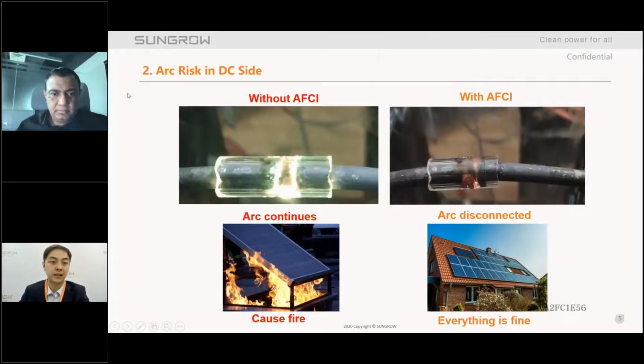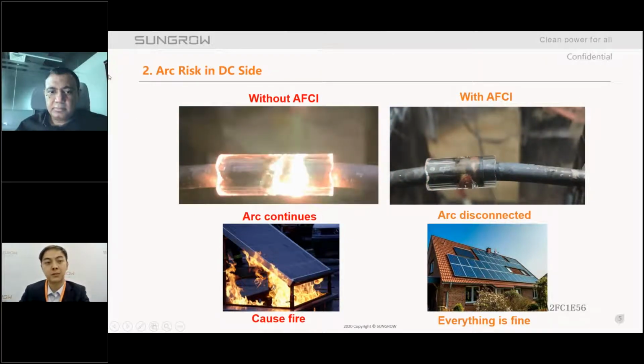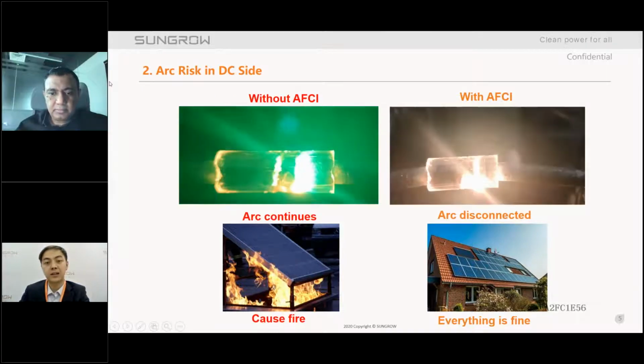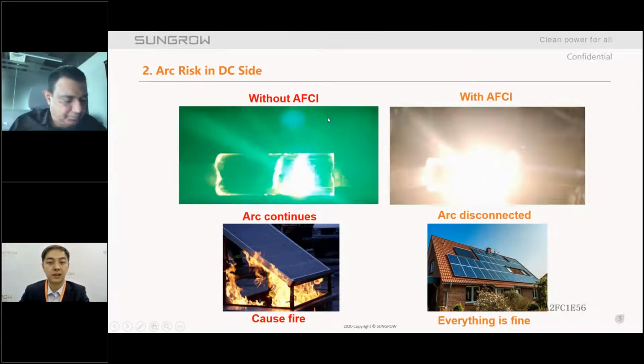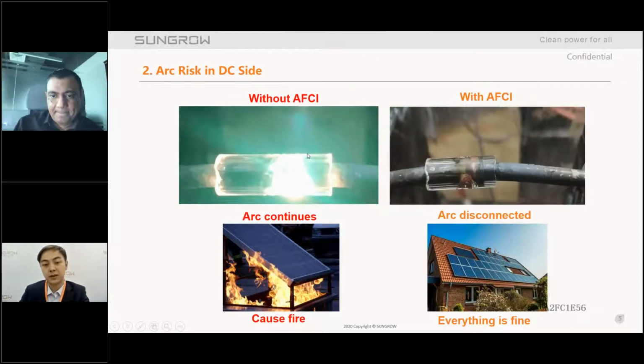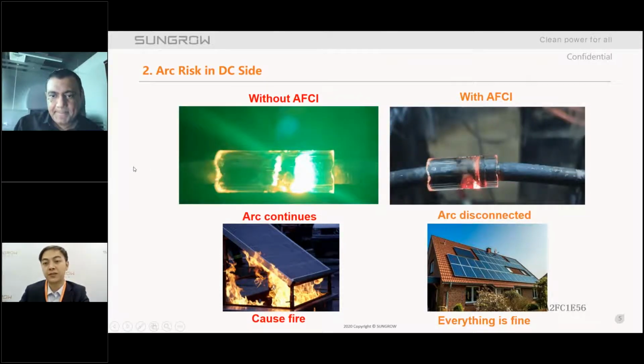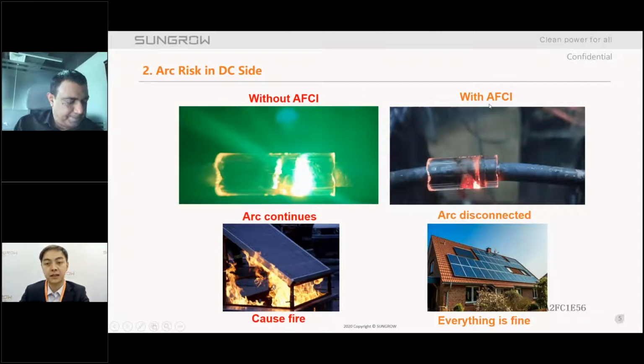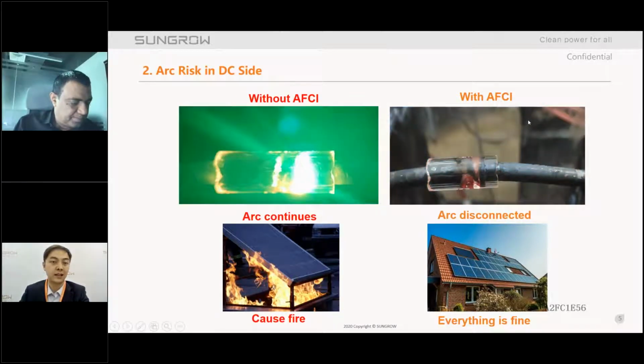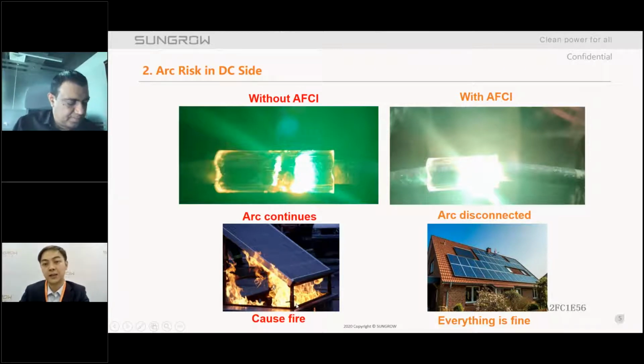In recent years, panels have gotten more numerous and cables have become longer. In this case, some plants may have a bad connection of the DC cable, or when the cable connection is in humidity, it will cause a small arc. If you have no AFCI function, this arc may continuously generate and may burn the panel or even the whole plant. But with AFCI, it can cut off this kind of arc and protect your plant safely. In case this kind of arc generates on the DC side, we have now updated our CX series with the AFCI function.